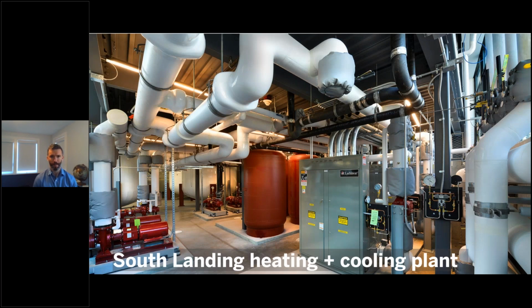Typically a high-performance building in a cold climate would be based on a ground source heat pump solution. Unfortunately, in our case, we were unable to identify or use a ground source resource. The open loop test well that we drilled was a poor performer. Vertical borehole was cost prohibitive because the site is located on basalt bedrock, and horizontal coupling also was eliminated due to cost and constructability challenges.